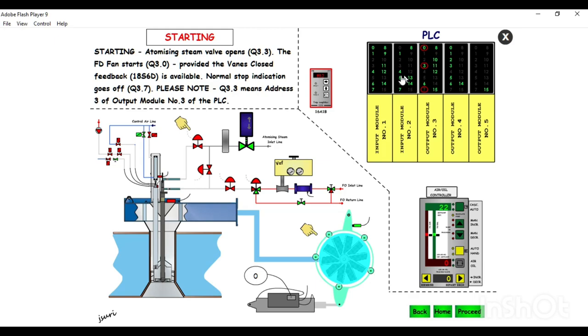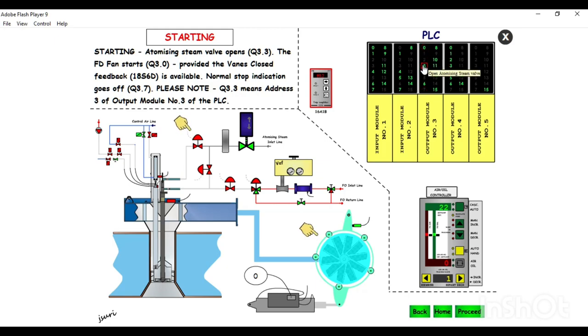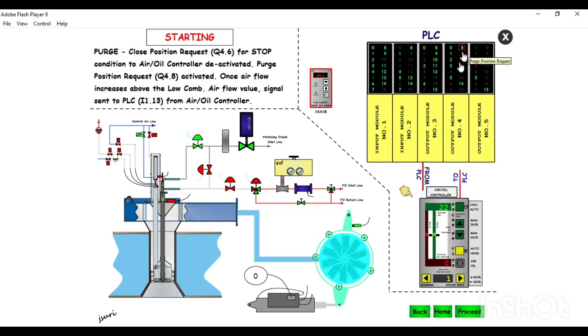Once the start signal is received at input module number one, it will initiate three outputs in output module number three of the PLC. Point zero sends an output signal to start the FD fan. Point three opens the atomizing steam inlet valve. Point seven indicates boiler burner normal stop status on the control panel. It will also check output number six and output number eight.